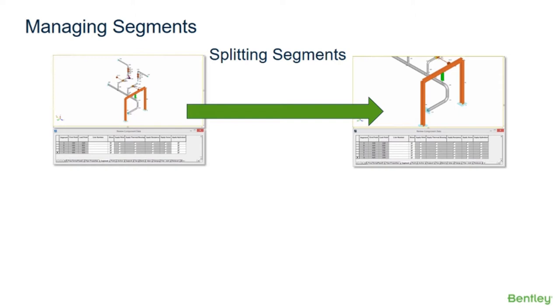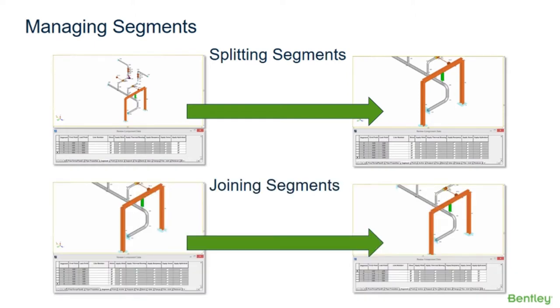The split segment command will split the existing point located on a common segment into two segments. Operations like the split segment command enable users to easily model piping which is or is not subjected to wind loading — for instance, indoor versus outdoor piping in one single model. It can also be used to break the model by splitting the segments and then deleting the point on one of the segments.